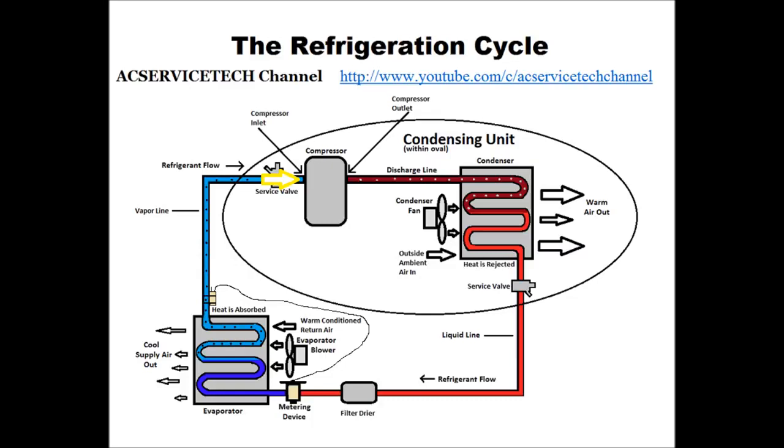So in the case of a thermostatic expansion valve, the valve is going to be controlling the superheat. But in the instance of a piston or an orifice or a capillary tube, you need to check the refrigerant charge in superheat. That's done right at the valve, typically by the compressor, and we're checking the total superheat. Typically, we're not getting a port right after the evaporator coil to check just superheat. We're checking the total superheat at the compressor.